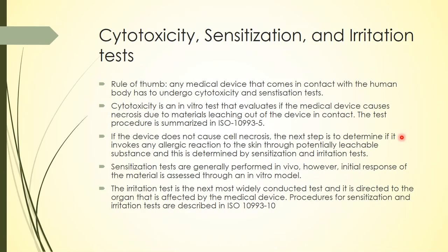So, cytotoxicity, sensitization and irritation tests. The rule of thumb is that whenever a medical device comes in contact with the human body, it has to undergo cytotoxicity and sensitization tests. Cytotoxicity is the death of the cell, right, wherever the medical device is implanted, the surrounding tissue should not be necrotized. That is the cytotoxicity test.